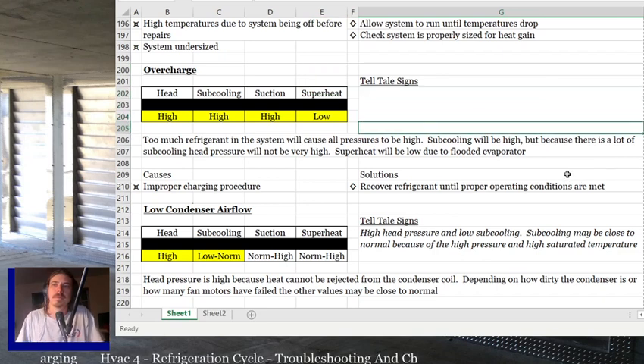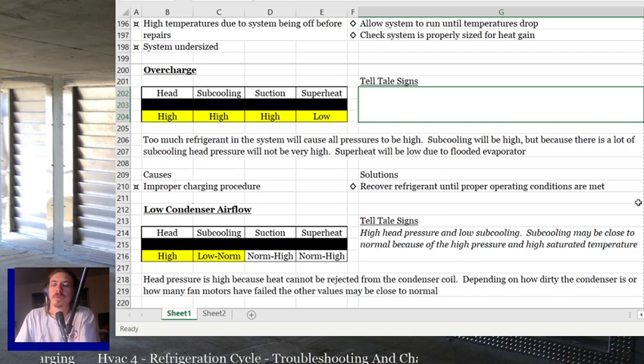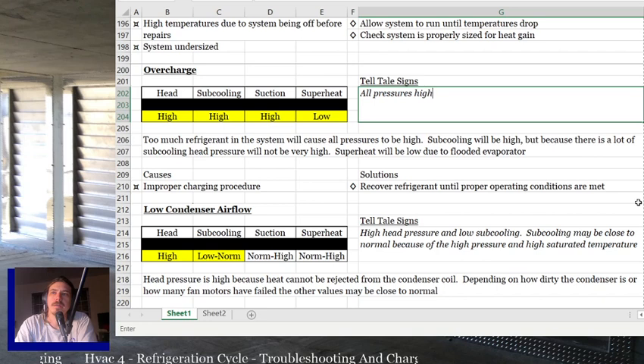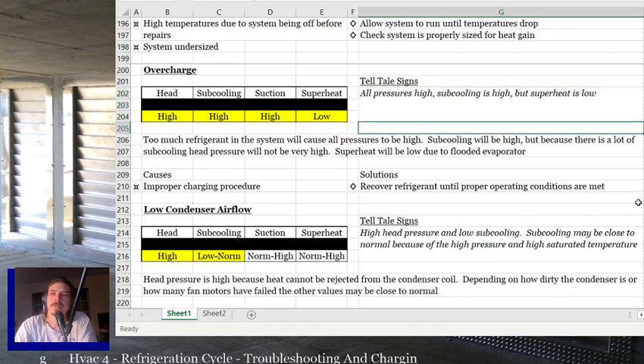What happened here? I got a feeling that was there before. So telltale sign: overcharge. Everything's high but superheat low. So all pressures high. Subcooling is high, but superheat is low. So an overcharge, I mean, it really doesn't get any simpler than that.